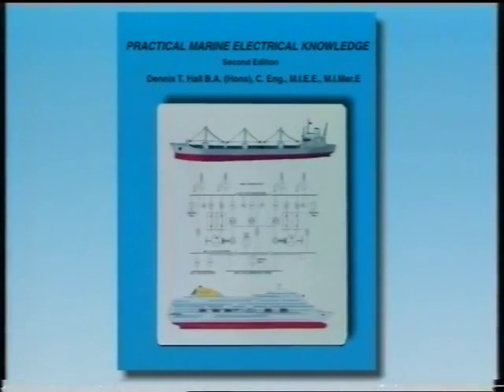Well, this concludes the subject of Programme 3. We've discussed a typical mains generating system and the automatic startup feature of an emergency generator. We've shown how to synchronize two AC generators and how to trace and test for a fault in the excitation circuit. We then showed how to reinstate residual magnetism and how to trace a fault in the AC generator rotor. Finally, we talked about an AC generator circuit breaker and dealt with fault tracing on a circuit breaker if it fails to close normally. We recommend that you watch this program again and that you consult the book Practical Marine Electrical Knowledge, which accompanies this series and will allow you to study certain aspects in greater detail. Finally, here's a list of contents for all the programs in the series.